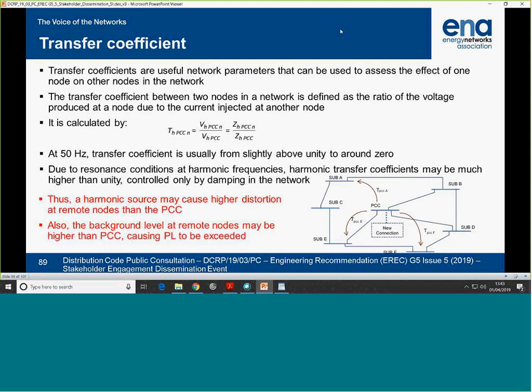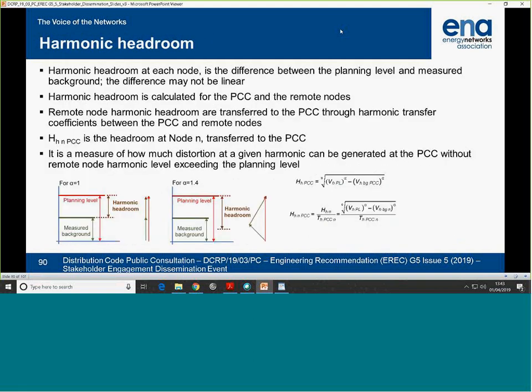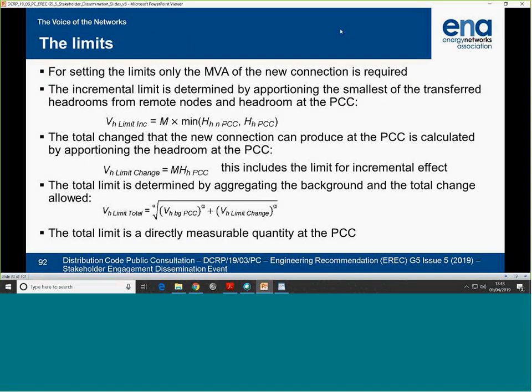It does. The volume is just based on the size of the connection and the headroom available locally. If there is a resonance, then the user has to make sure that it complies with this. Okay. If the resonance locally causes non-compliance against this, then they have to use mitigation. Okay. Thank you.